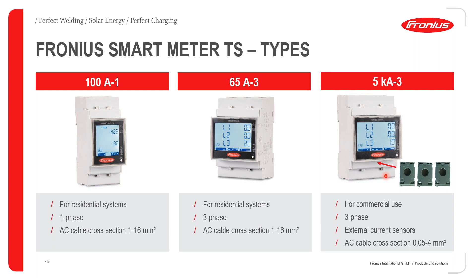Then we have the industrial smart meter for industrial purposes, which has an ampacity of 5 kiloamps per phase. But since this is a high figure in terms of current, we would need current transducers to step down this high current to a much more friendly current, usually 1 or 5 amps.